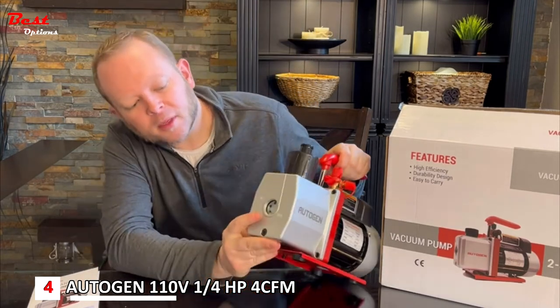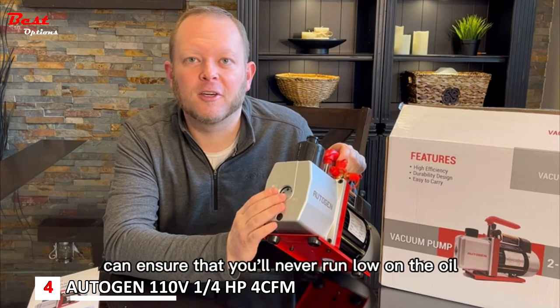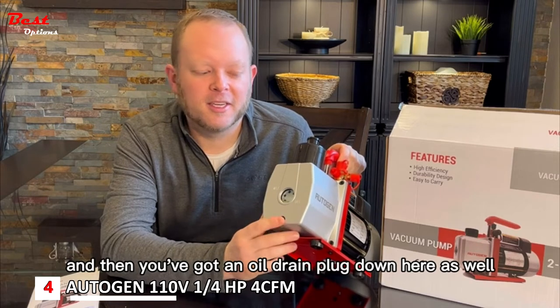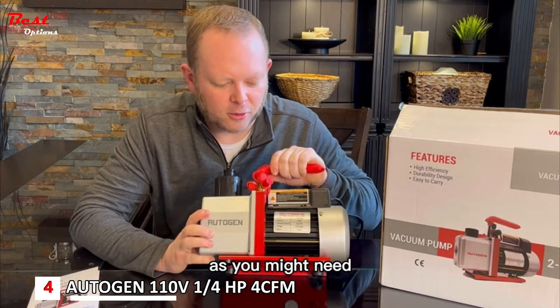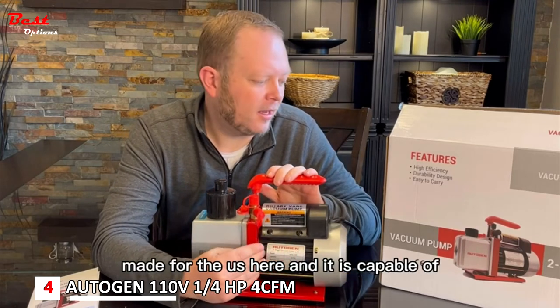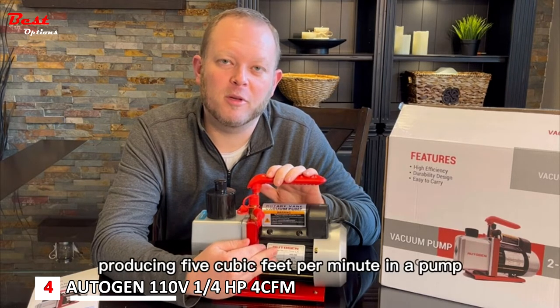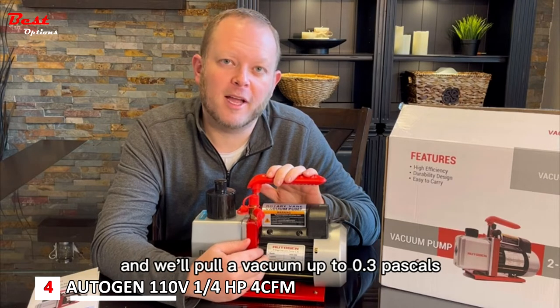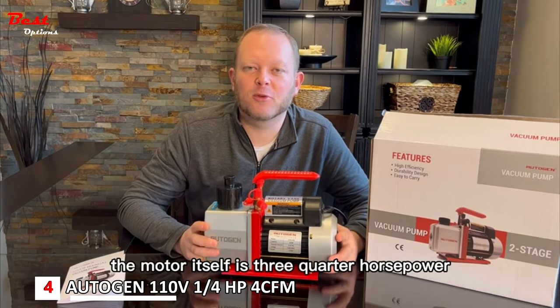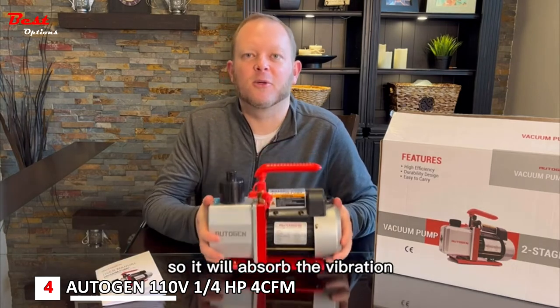This is a two-stage vacuum pump and it also has a sight glass so that you can ensure you'll never run low on the oil. The oil is the critical part in the pump, and then you've got an oil drain plug down here as well to do an oil change as needed. The motor is 110 volts, made for the U.S., and is capable of producing five cubic feet per minute and will pull a vacuum up to 0.3 pascals. The motor itself is one-quarter horsepower. It has rubberized feet on the bottom to absorb vibration.